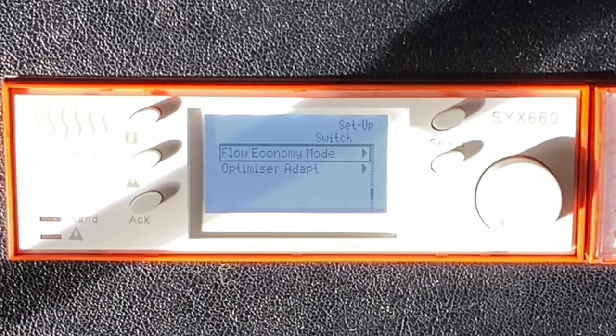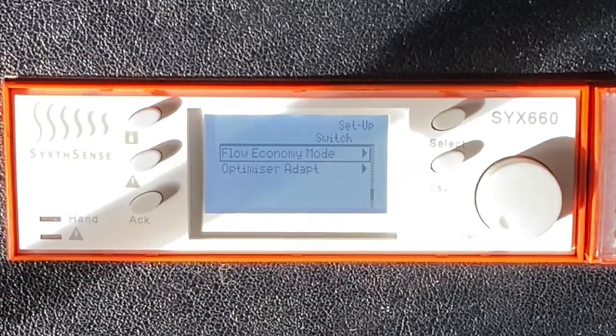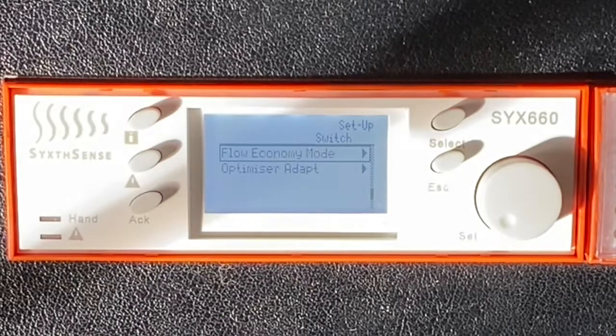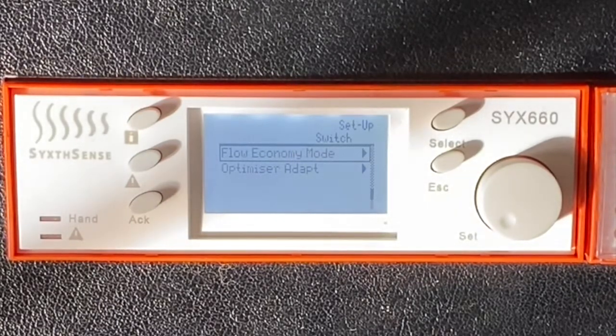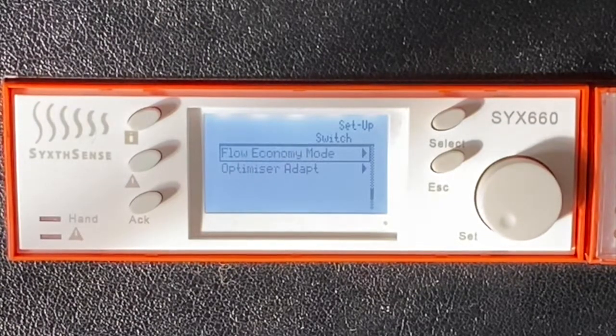Flow economy mode. This is a feature of the controller where it looks at the calculated flow set point and it's looking at the current room temperature. If they are within 7 degrees of each other, based upon the slope of the heating curve, if we end up with a calculated flow set point which is very close to the current room set point, then there's little point in running the heating plant to service that demand. So the controller will go into an economy mode, which is saving energy because there's little purpose of running the plant to service such a small demand.